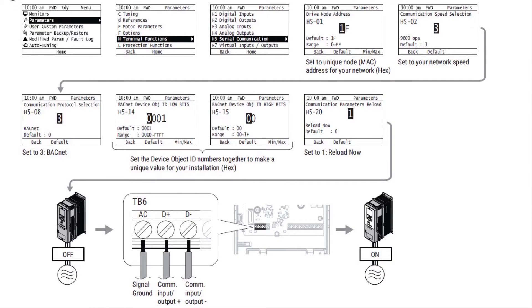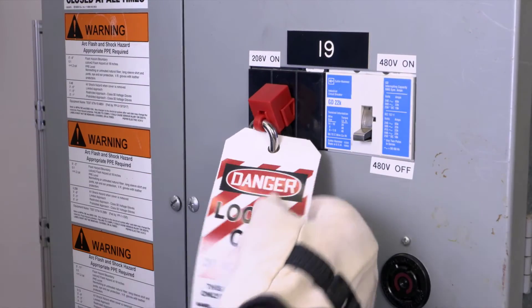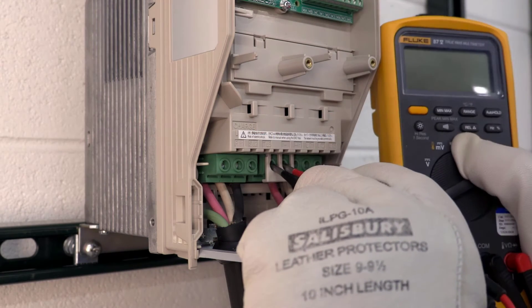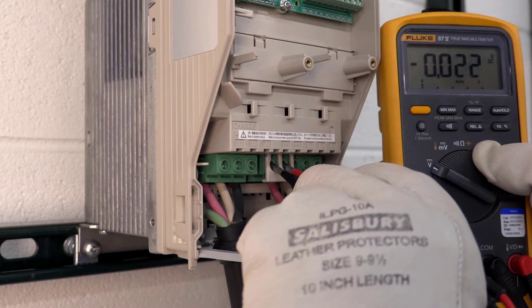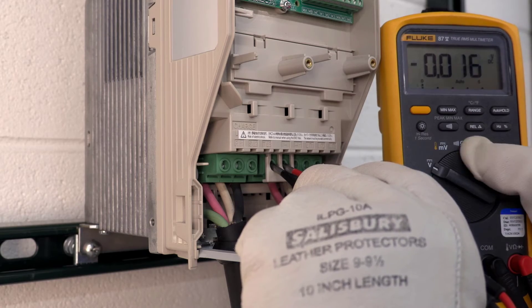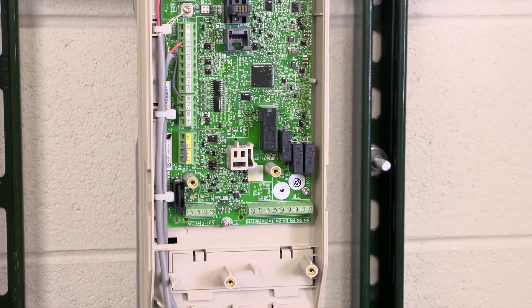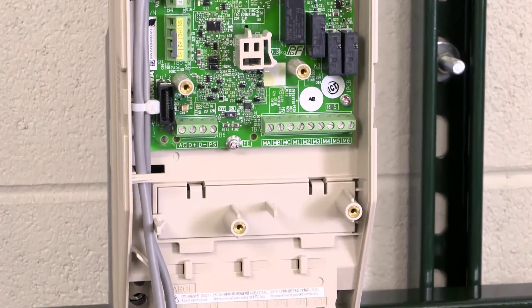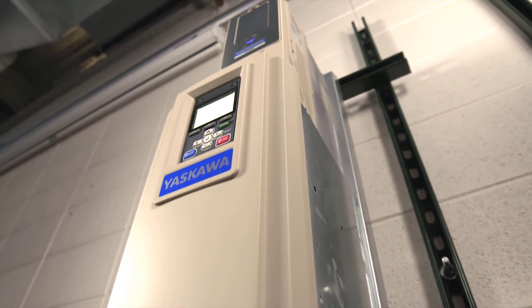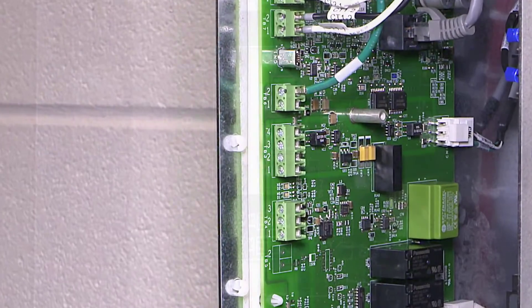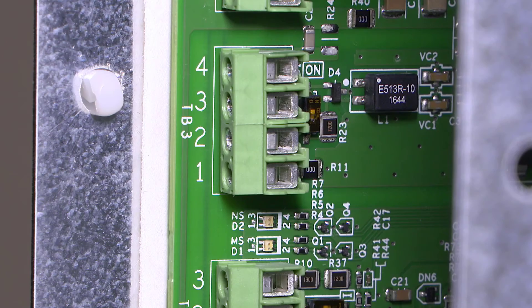Wiring is made easy whether you're using an HV600 drive or bypass. Confirm that all power sources are turned off, all devices are discharged, and you have performed the correct lockout/tagout procedure before doing any wiring. When wiring a drive, locate the TB6 terminal block on the drive control board. If you are setting up a bypass, locate the bypass control board and use the TB3 terminal block.